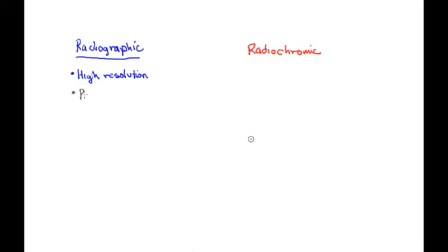But that comes also with some disadvantages. One is the processor that's needed to pull that latent image out. There's a lot of chemicals, a lot of materials. There are some other disadvantages. But let me just describe how you would pull out a dose from these films, and this is true of all the films. You have some light coming in with some intensity I0, and then light coming out with some intensity I. So you're basically looking at how much the film absorbs that light.